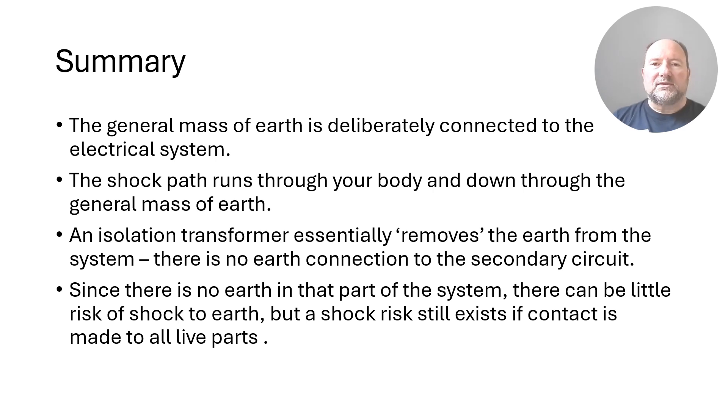And that's usually going to be the Earth neutral point of the secondary winding in the distribution transformer. An isolation transformer then essentially removes the Earth out of the system, just gives you two live conductors.